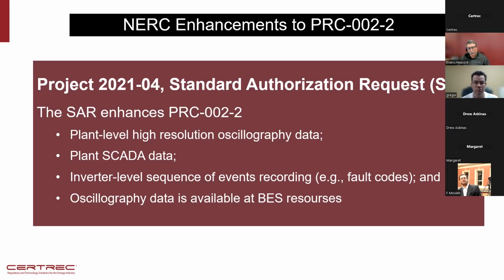So their long-term plan is to make sure that plants do have high-resolution oscillography data recording, plant SCADA also recording if they have that, and inverter-level sequence of events recording, having fault codes as part of that. And then also make sure the data is available at the BES resources so that they can actually provide this to others. And this is actually one of the main recommendations out of the standard and the review of the event that was put out by NERC back in December.